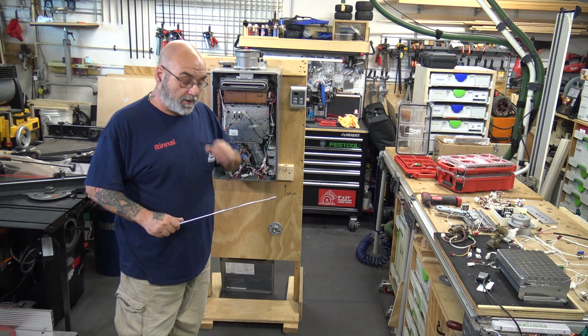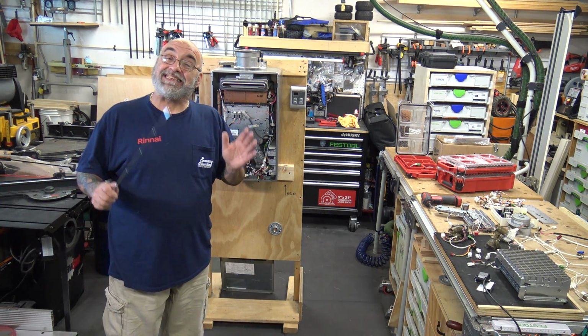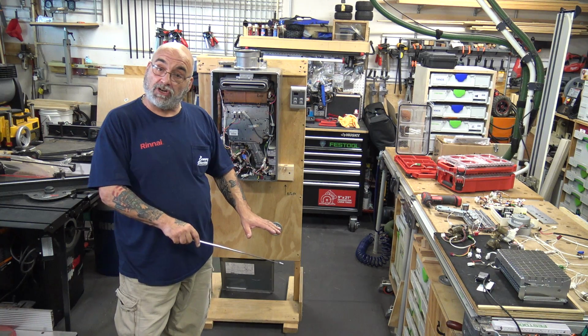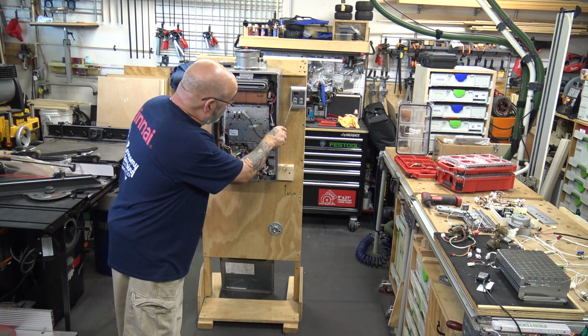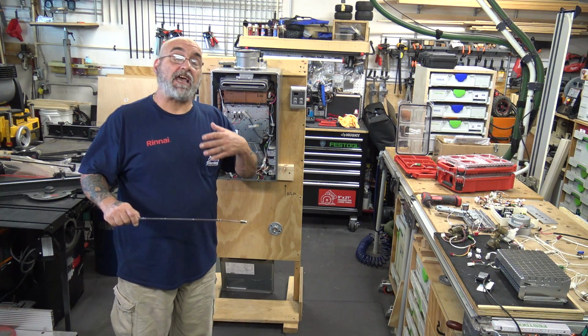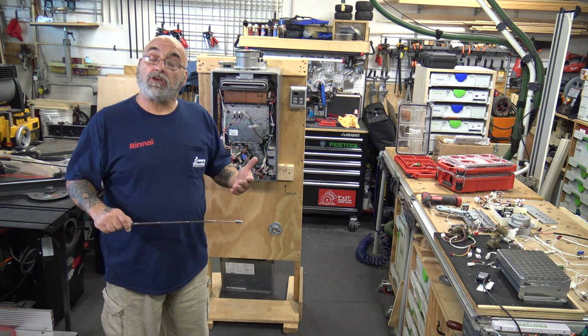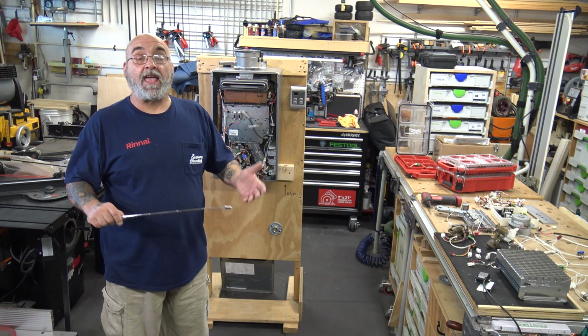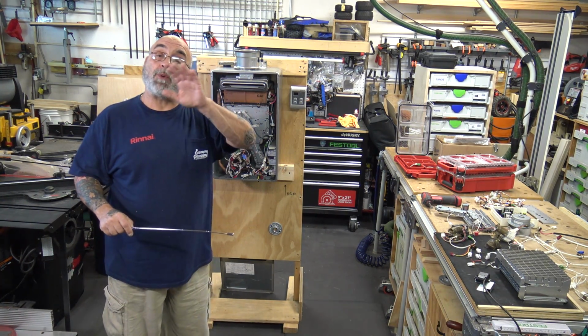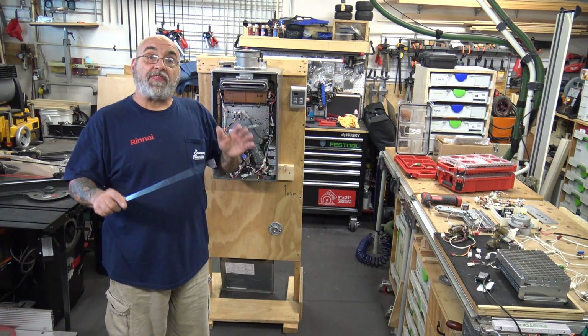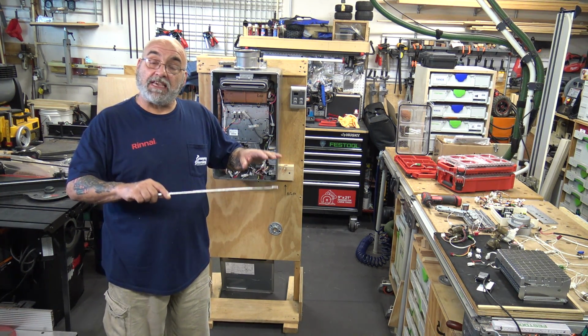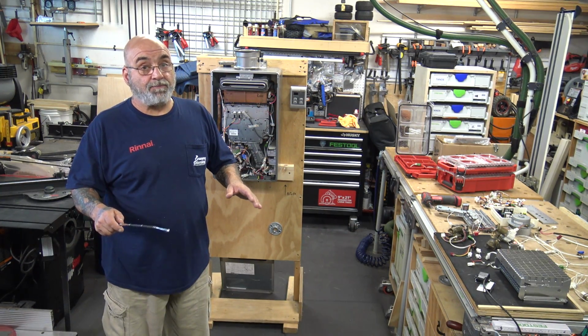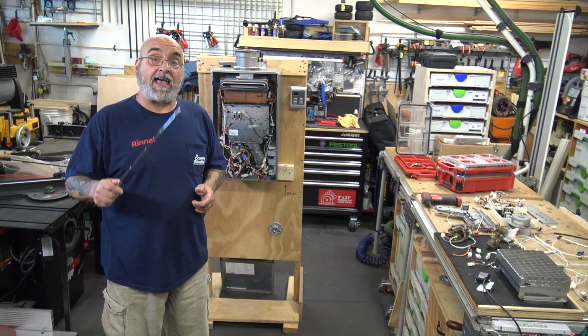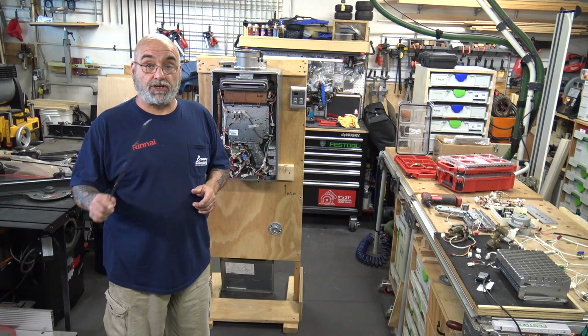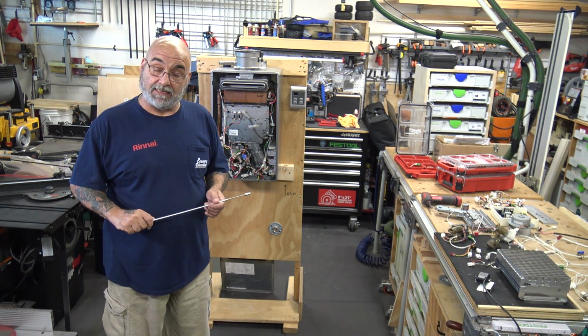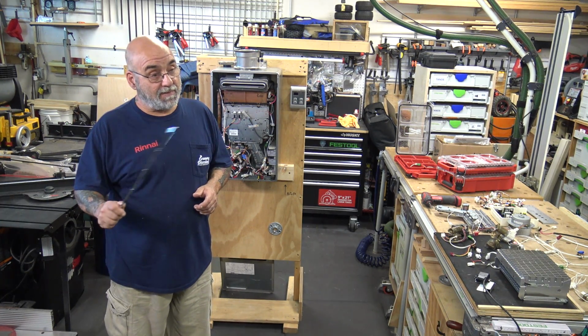Now, I've talked about before a thing called the delta T. That is your groundwater temperature in comparison to what you have the controller set at. So let's just say you have 70-degree groundwater temperature and you have this set at 120. So you have a 50-degree delta T. That delta T drops the gallons per minute down, not by a lot. You can actually Google it and they will give you the formula on how to determine what your delta T is. Again, if we go over that, lunch and a pillow.